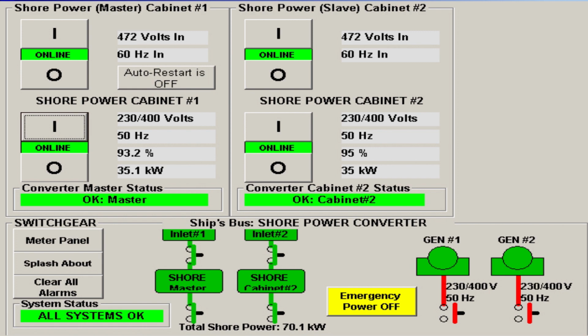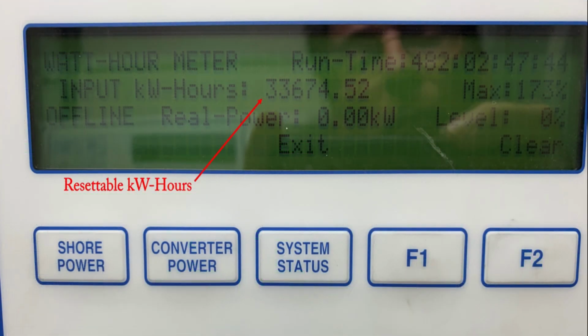Another advantage to most frequency converters is that they have resettable kilowatt meters, like the trip meter in your car, so you can track your power consumption at each marina. In some parts of the world, it's not uncommon for the cost of power to be higher than the cost of dockage. We have found on many occasions that marina meters would read anywhere from 10 to 15% high.